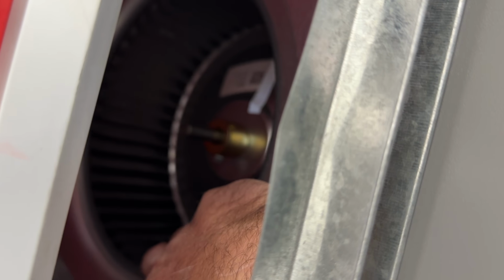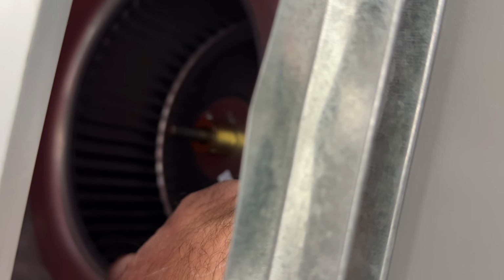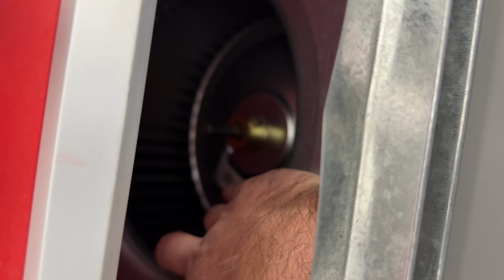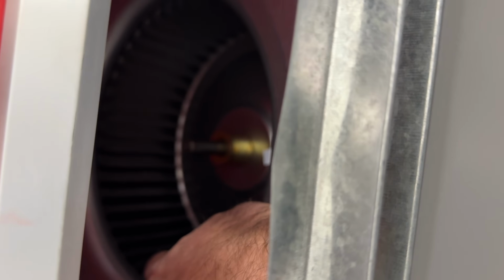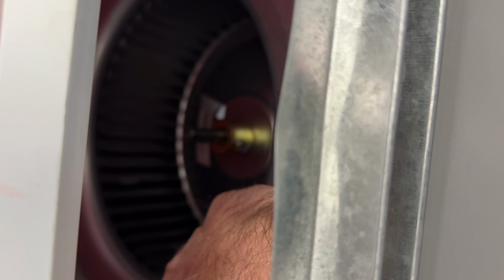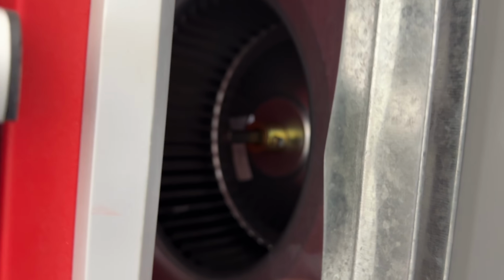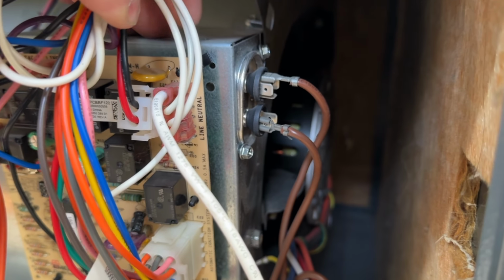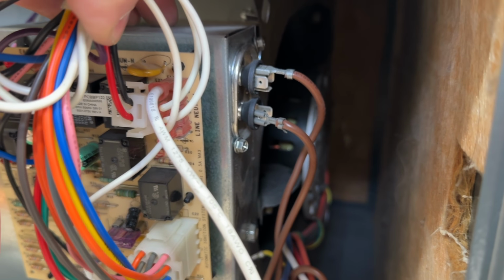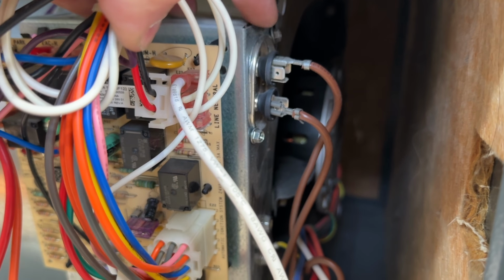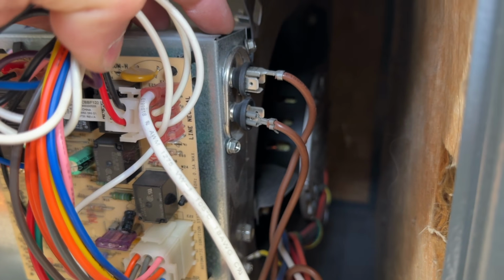If that spins pretty freely and there doesn't seem to be any resistance, then your blower motor is probably not bad. If it is bad, it will probably be kind of seized up and it'll be hard to spin. So if this has resistance, you probably need a new blower motor. But something else that you can check is the capacitor, and it looks like this right here. Now be very cautious because these can retain energy.